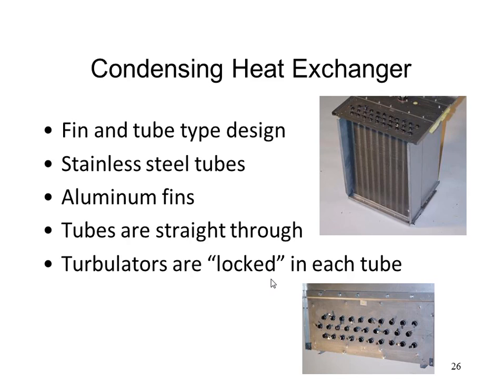So there's lots of little things that contribute to this guy being the most efficient furnace you can get. The modulating gas valve obviously helps. The little turbulators help. The aluminum fins help. The more surface area on the heat exchanger than we used to have helps. So a lot of things working together there.